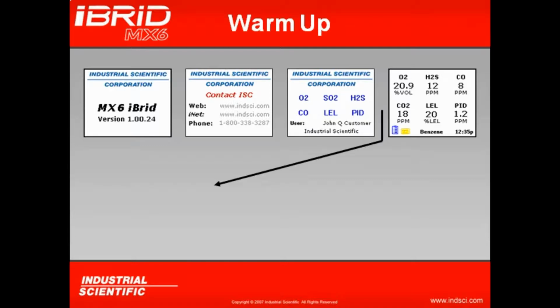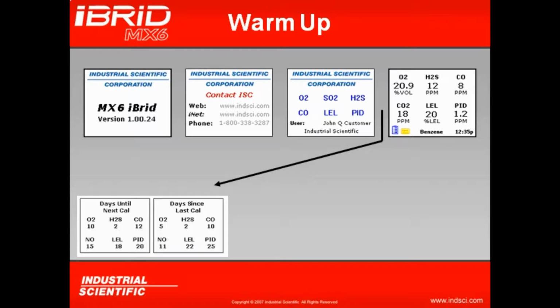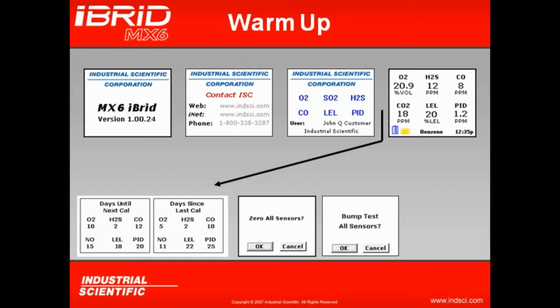These optional screens will appear if the instrument has been configured to show such screens. The first screens that may appear might show you either days until or the days since last calibration. Another screen that may appear if programmed may ask the user to zero the instrument during startup. The next screen up may ask us to bump test the instrument prior to use.